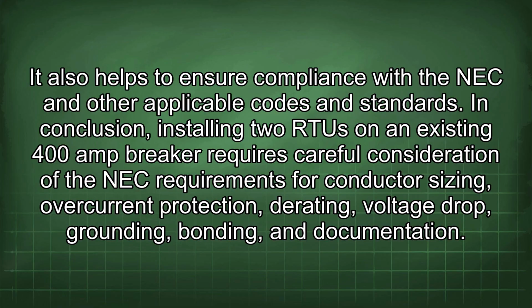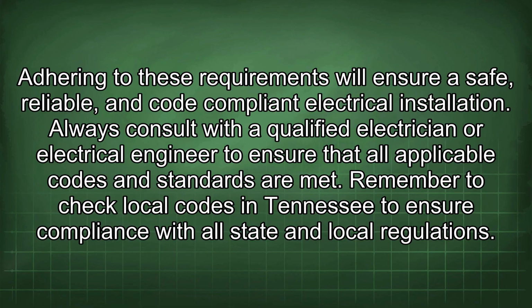In conclusion, installing 2 RTUs on an existing 400 amp breaker requires careful consideration of the NEC requirements for conductor sizing, overcurrent protection, derating, voltage drop, grounding, bonding, and documentation. Adhering to these requirements will ensure a safe, reliable, and code-compliant electrical installation. Always consult with a qualified electrician or electrical engineer to ensure that all applicable codes and standards are met.